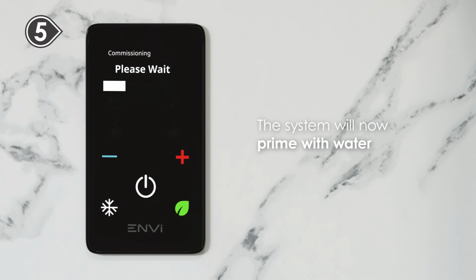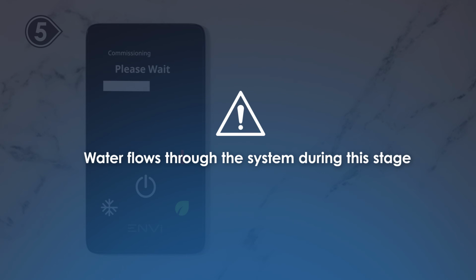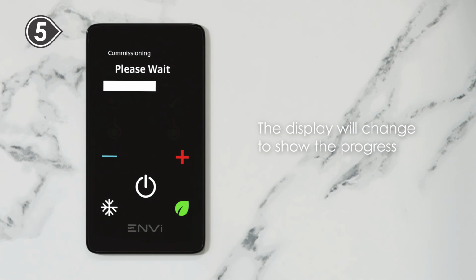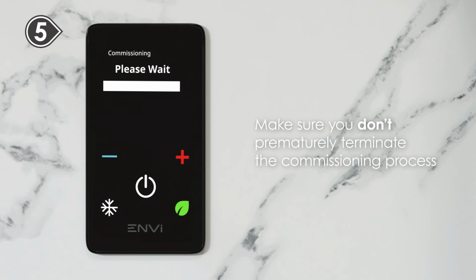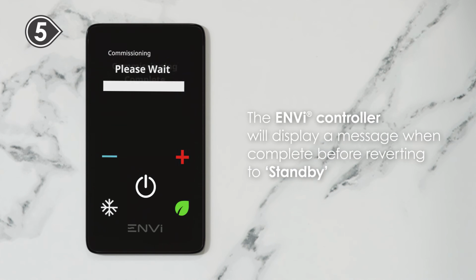The system will now prime with water and undertake an important routine to prepare the Tri-Hub for use. Keep in mind that water flows through the system during this stage. The display on the ENVi controller will change to show the progress. It'll take around 2 minutes to complete. Make sure you don't prematurely terminate the commissioning process. The ENVi controller will display a message when complete before reverting to standby.